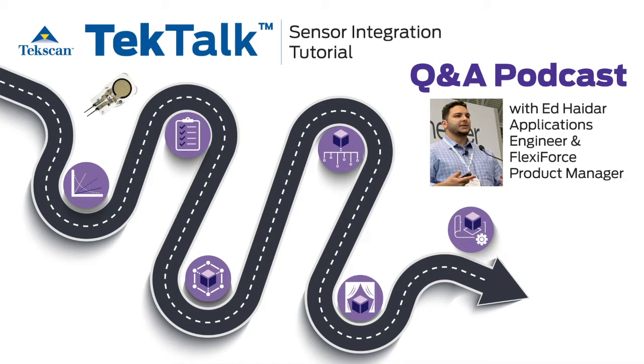Tekscan manufactures and designs sensors to maintain their linearity through a wide gamut of force ranges. When we're talking about the absolute maximum that a FlexiForce sensor can withstand before plastic deformation occurs, you're talking about somewhere in the 10,000 psi pressure range. We like to give that number in terms of contact pressure because, of course, the contact area could be variable from application to application. So the 10,000 psi mark is where we could start to see some permanent and plastic deformation in the sensor itself.